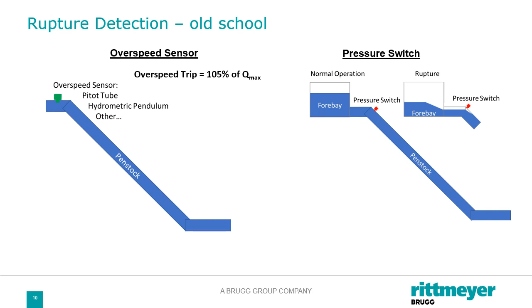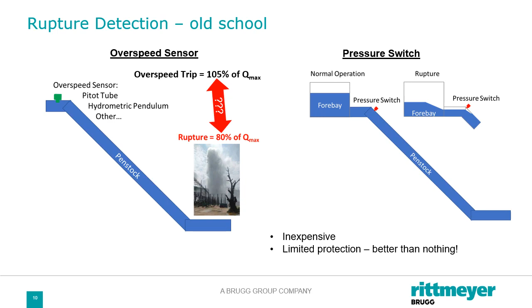In all cases, an overspeed sensor is only going to detect a rupture if it exceeds the maximum flow that you're ever expecting for that system. If you have a large penstock, then even if it's only a rupture of 80% of the flow, it could still be quite catastrophic, and an overspeed sensor will never see it. So they're inexpensive, they're cheap and cheerful, they are better than nothing, but they're of limited utility.